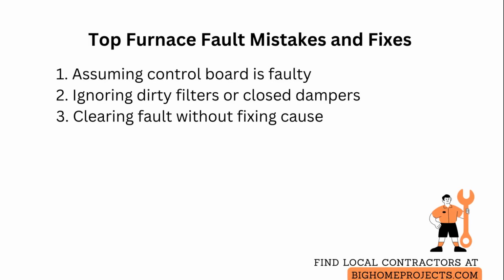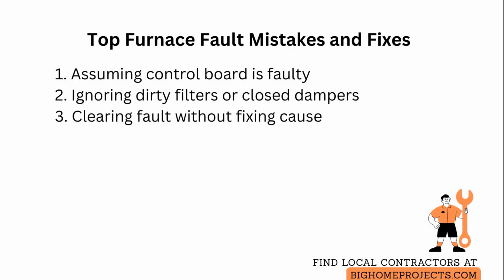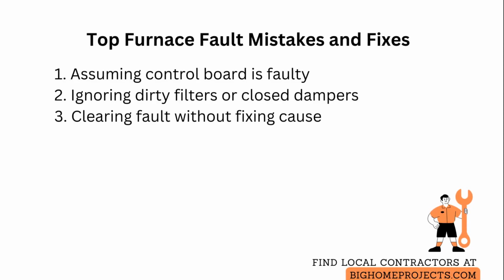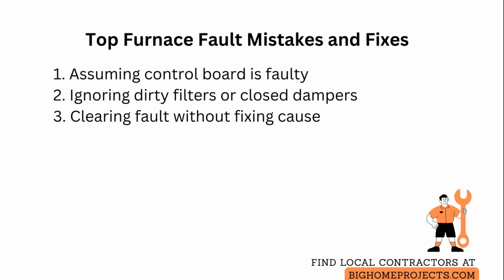People sometimes clear a fault without addressing the underlying cause and the problem returns. Restore limits, repair any failed parts, and run the system long enough to confirm temperatures stabilize before declaring the issue fixed.